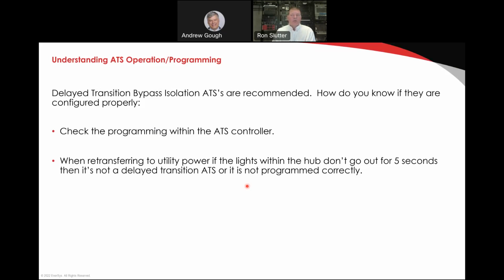So if when you return to utility and you hear the ATS transition and the lights slightly blink, that's what we call closed or open transition. It's not delayed. A delayed transition will turn the lights off for, like I said, recommended time of 5 seconds before they return to the utility source. So that's a good way to know what's going on in your facility and having an idea what kind of ATS. Now, there could be a situation where your delayed transition ATS is not programmed for the correct scenario. Again, there are 40 something settings in an ATS.